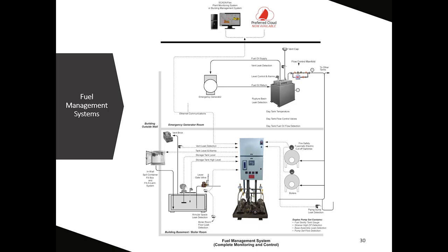Example of a control system for our fuel system showing pump set control, tank gauging, leak detection, and overfill alarm. Fuel oil system controls can be as simple as a hand-off-automatic switch or as complex as a PLC-based system. The main advantage to the PLC is that they can talk to your building management system or a cloud-based system.